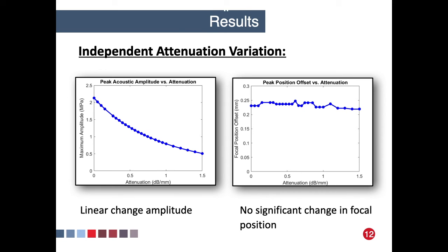Based on our results, there is an exponential decay of the peak acoustic amplitude as a function of the attenuation coefficient, which is somewhat expected given the exponential nature of attenuation in the skull.